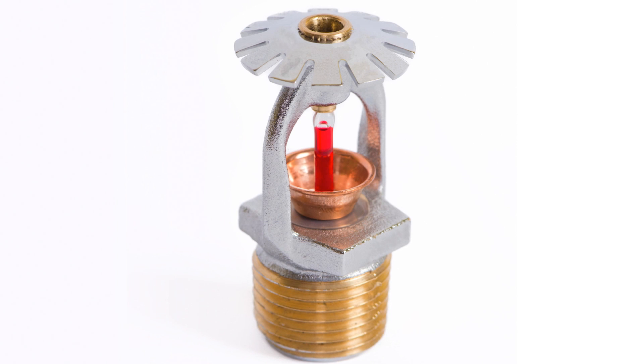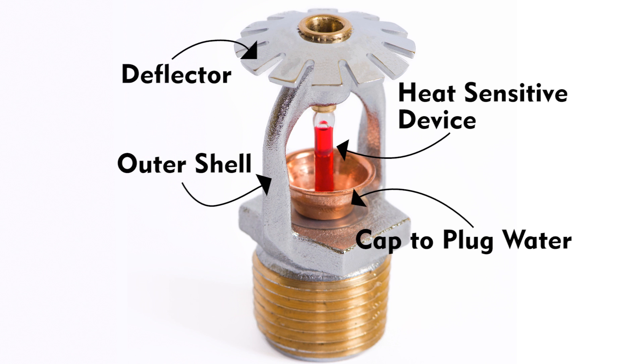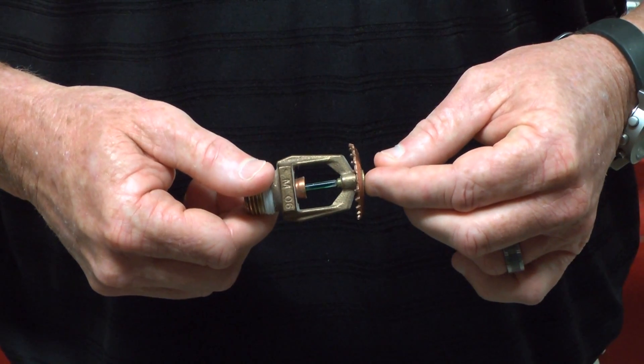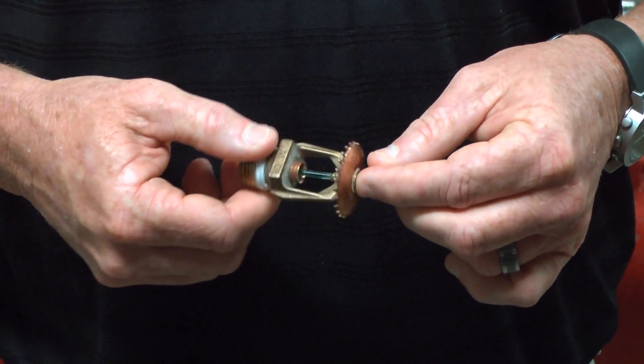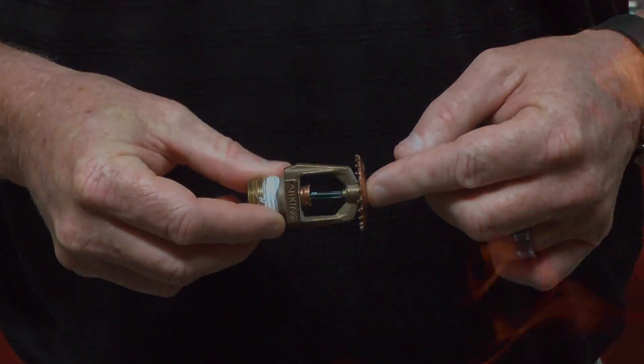The sprinkler head is the central nervous system of a sprinkler system and the part everyone is probably most familiar with. There are many different types of sprinkler heads, but they all share the same components: an outer shell, a cap to plug the water when not in use, a heat sensing device, and a deflector that allows the water to make a cone-shaped spray. In most systems, individual sprinkler heads are triggered by a heat sensitive device built into the head.